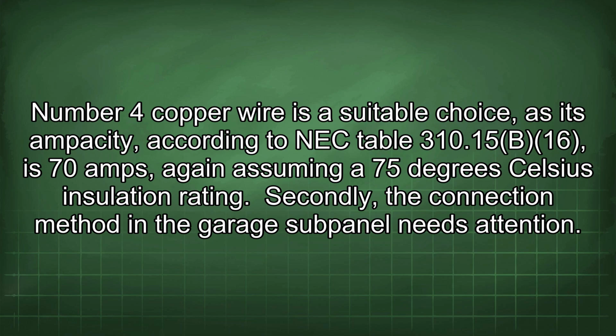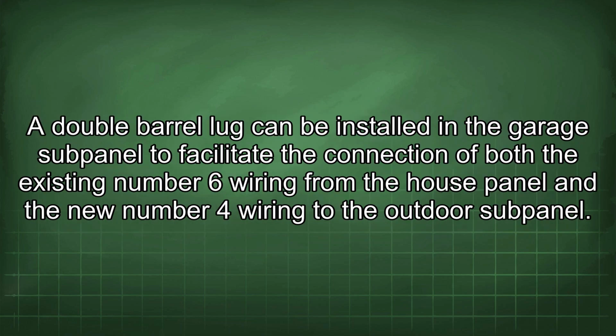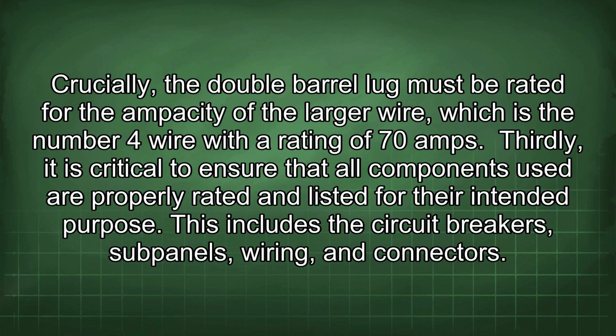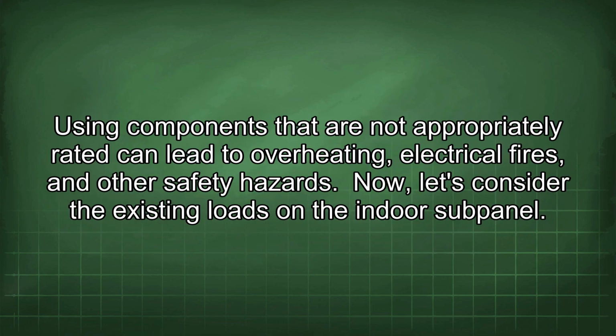Secondly, the connection method in the garage subpanel needs attention. A double barrel lug can be installed in the garage subpanel to facilitate the connection of both the existing number 6 wiring from the house panel and the new number 4 wiring to the outdoor subpanel. Crucially, the double barrel lug must be rated for the ampacity of the larger wire, which is the number 4 wire with a rating of 70 amps. Thirdly, it is critical to ensure that all components used are properly rated and listed for their intended purpose. This includes the circuit breakers, subpanels, wiring, and connectors. Using components that are not appropriately rated can lead to overheating, electrical fires, and other safety hazards.